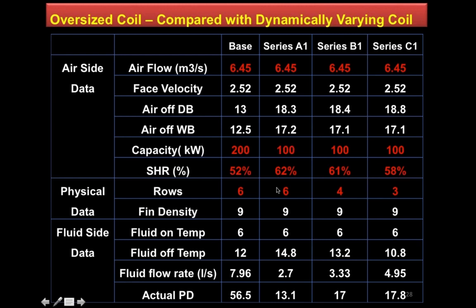And when I try to use the same 6-row deep coil, I'm looking at a 62% sensible heat ratio. The smaller the number, the better it is for dehumidification. The higher number means that I am compromising on dehumidifying performance. Then I try to see if I can change that to a 4-row deep coil. Well, not that significant, not that big an important change.